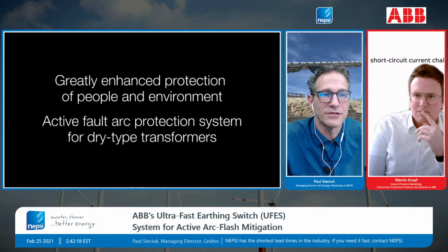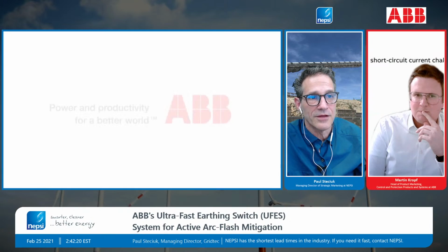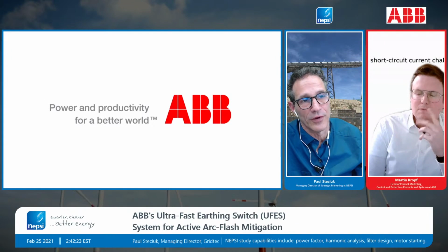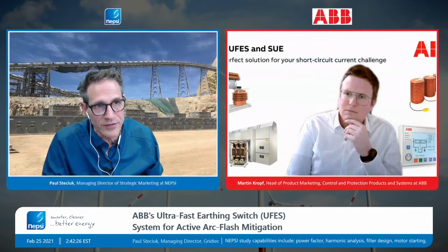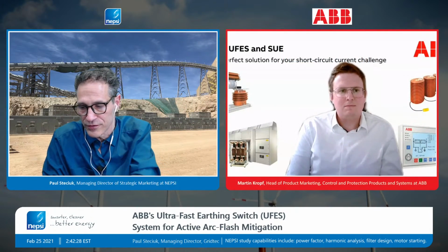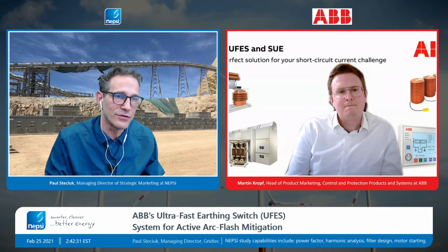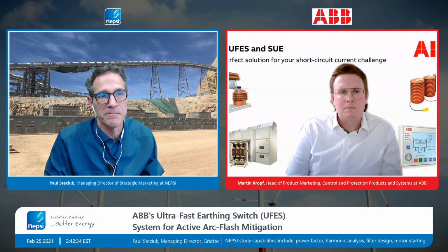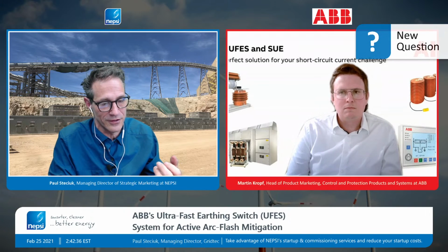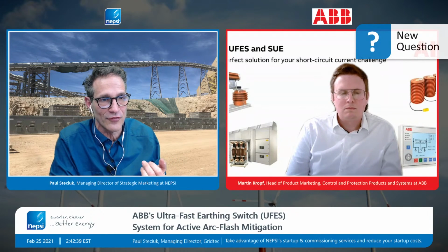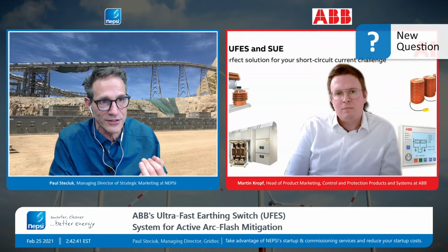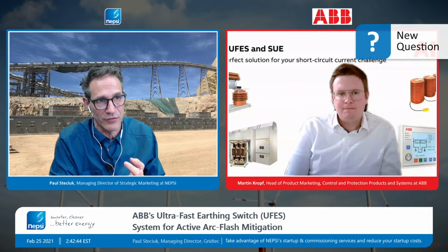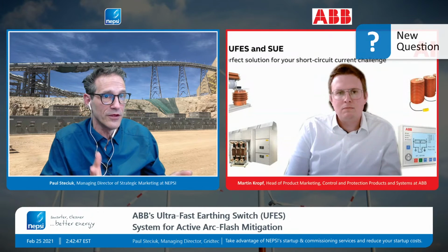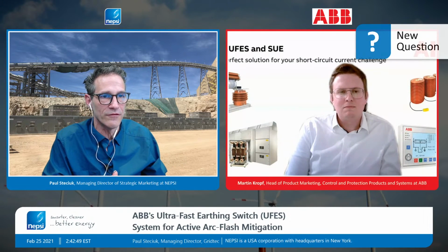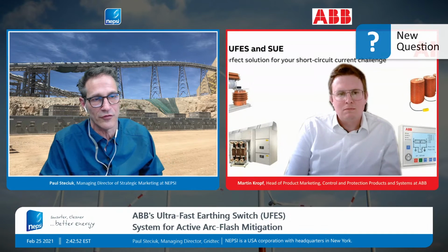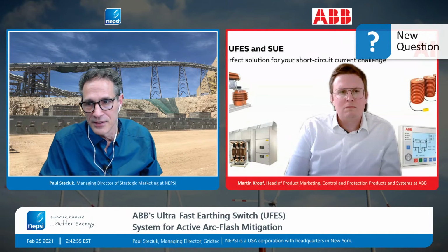The situation is that the transformer could have failed—you might have to replace it, the windings might have been damaged. But with the ultra-fast earthing switch in there, perhaps you would have saved the transformer. It could have been a faulty lightning arrestor inside the transformer housing, or a bad termination, causing collateral damage. So a lot of things unrelated to the transformer failure could result in it being damaged and having to be replaced. So, we got some more questions.